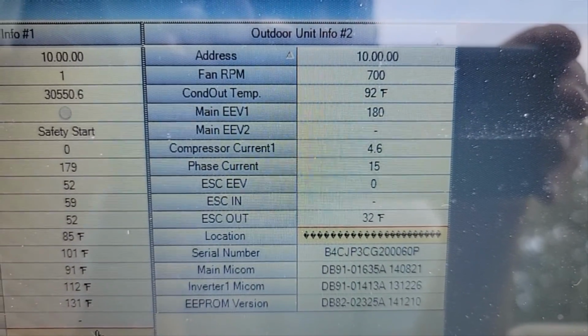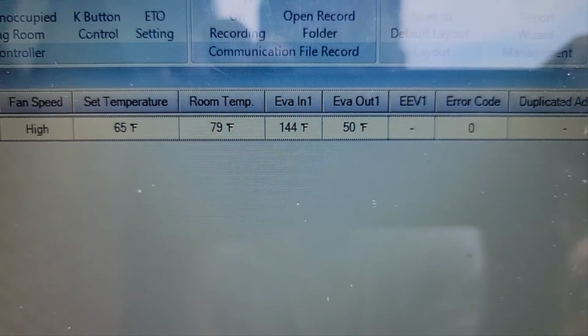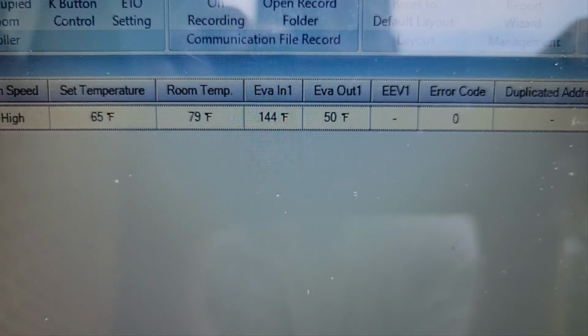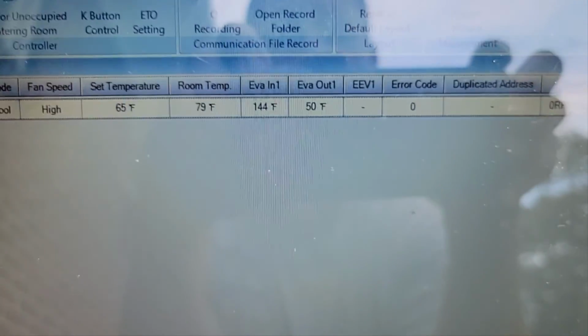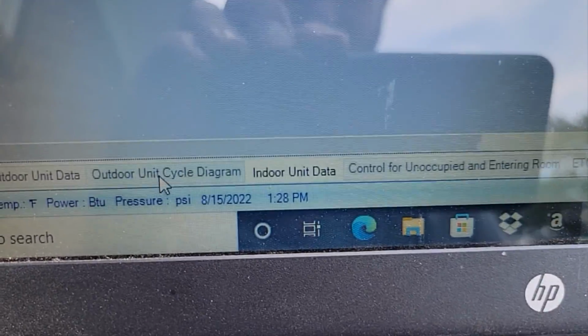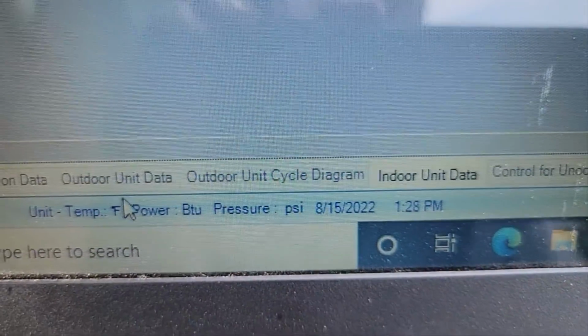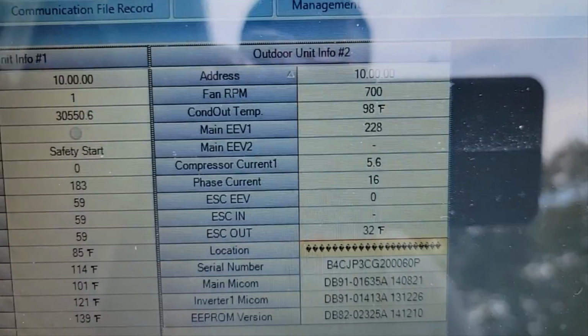EEV is 180. Indoor unit data, evaporator outlet is 50 degrees, and evaporator inlet says it is 144, which is ridiculous. Outdoor unit data, go back to the EEV, 228 still.